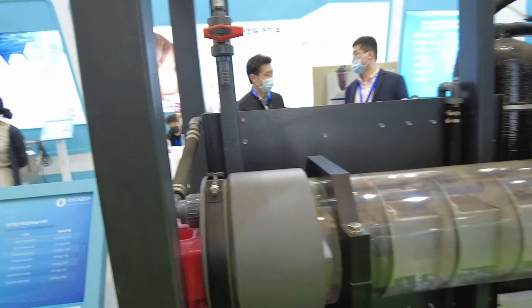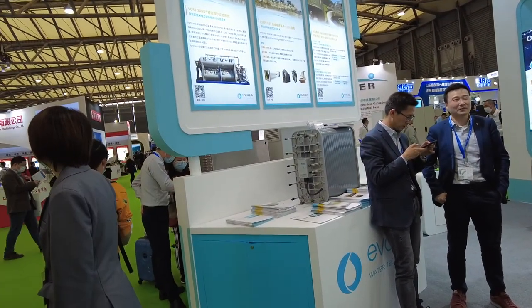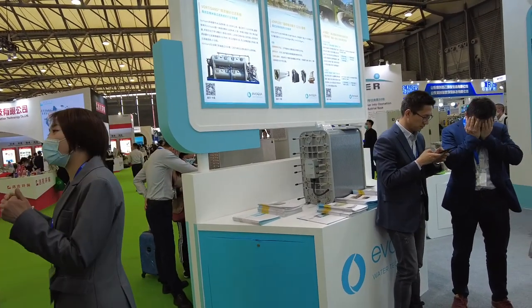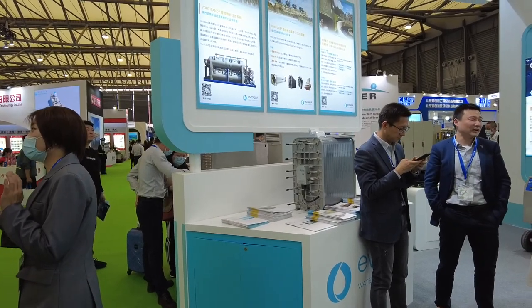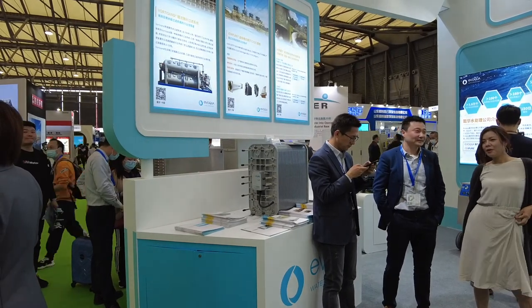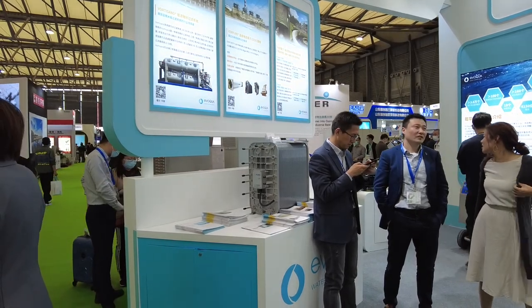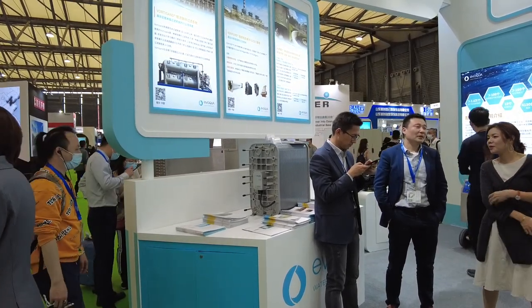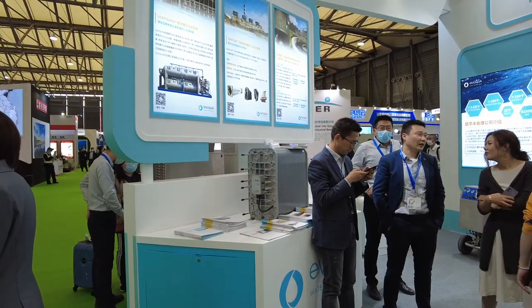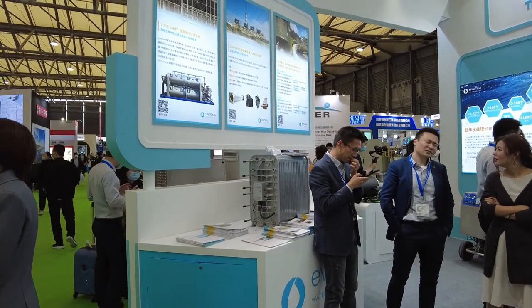We do completely different for ultra pure water. Okay. And this is an EDI. We call it electro-deionization. Basically for a UPW system, you have it for electronics, boiler water for power plants. You need to take out all the minerals. Correct. So usually you use some multimedia filter first, just to get out the sediment. And you use UF, and you use RO. But RO doesn't filter out everything. No, it doesn't. This is the last part, so it takes out all the rest, the polishing.